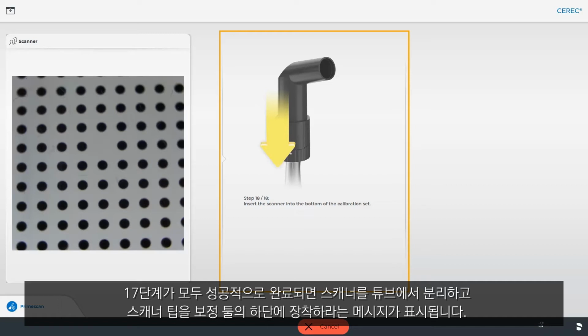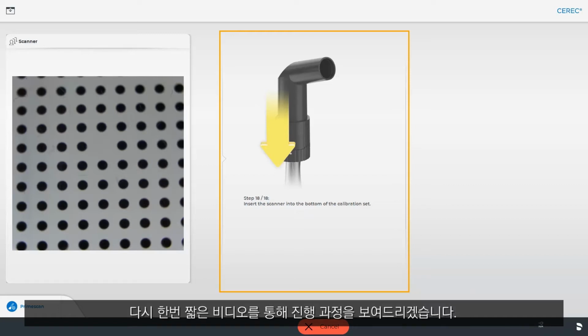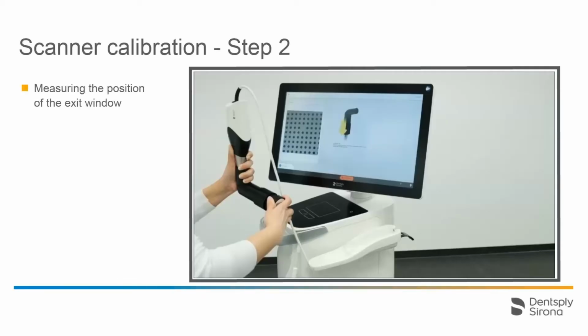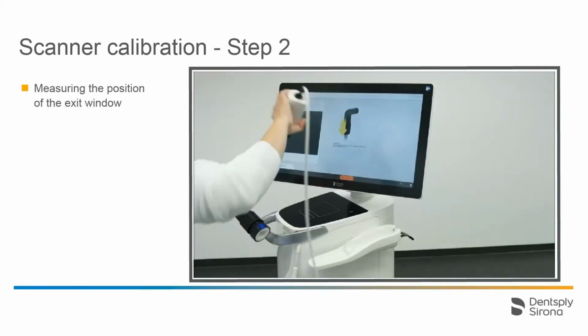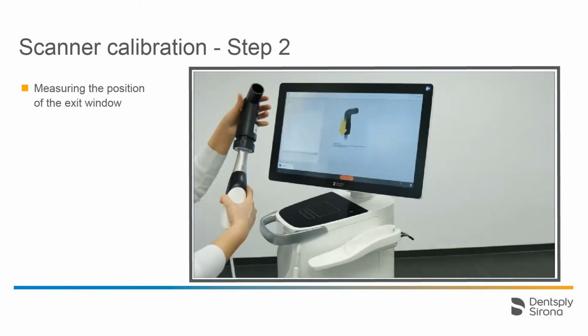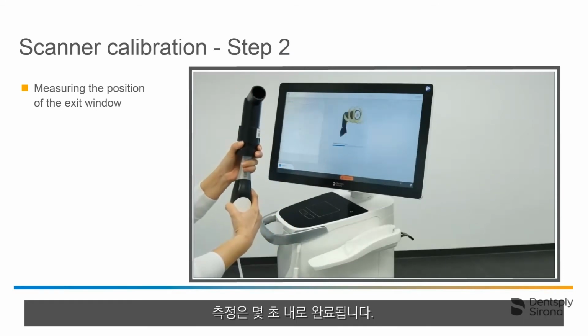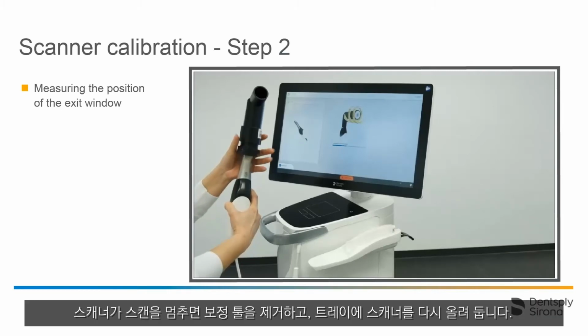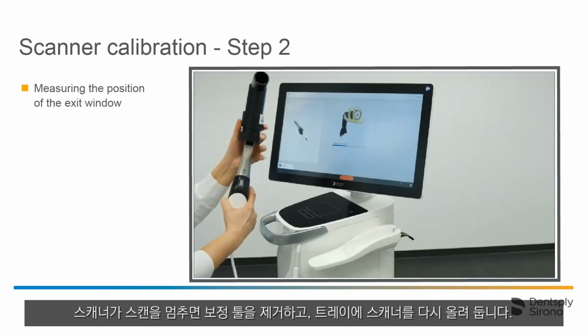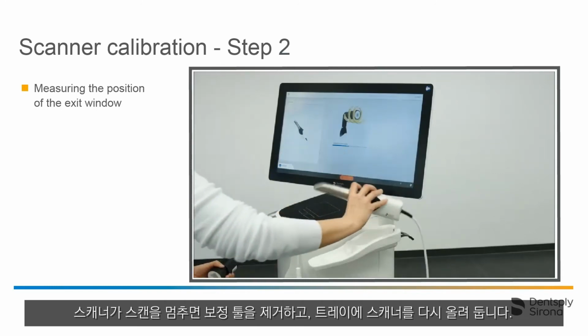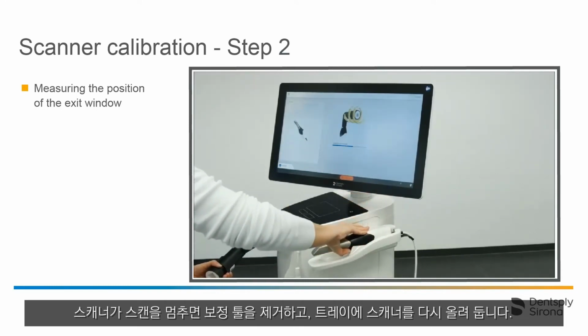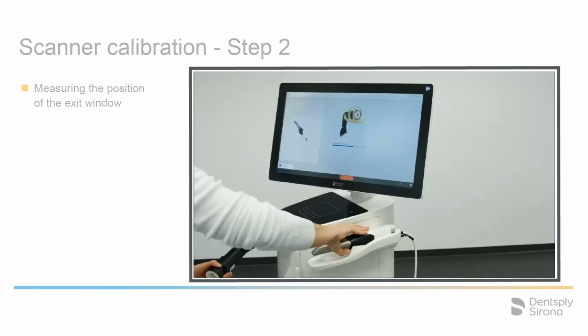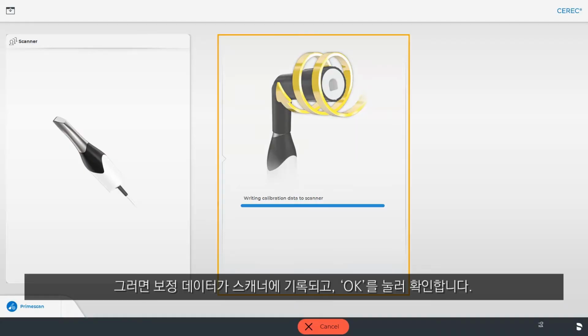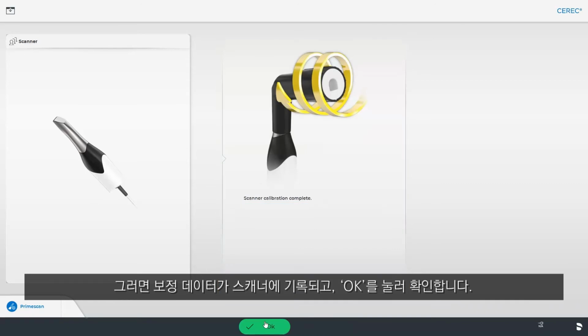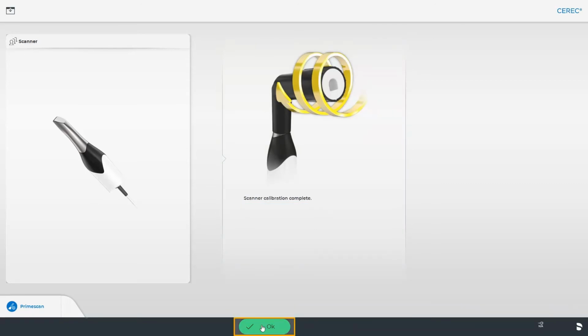This measures the position of the exit window. Now, once again, a short video that illustrates this process. The measuring only takes a few seconds. Once the scanner stops scanning, the calibration set can be removed. While the calibration is being calculated, the scanner can be placed back in the tray. The calibration data is then recorded to the scanner, and we confirm with OK.